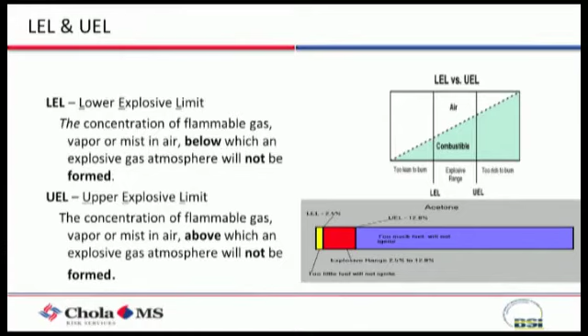Here if you see, the percentage compositions are different, so you will have the explosion range between those levels. What does it mean for each and every flammable product, liquid or whatever flammable liquid, the LEL and UEL will be varying. Based on which flammable liquid or solvent we are handling, we need to measure the LEL accordingly. When putting a gas detector, we need to consider these values before placing the LEL gas detectors inside the process block.